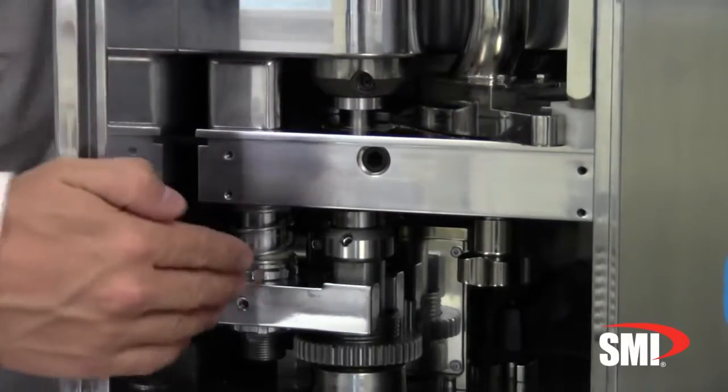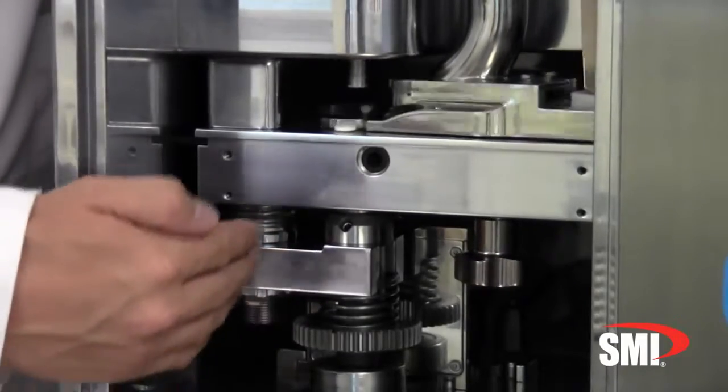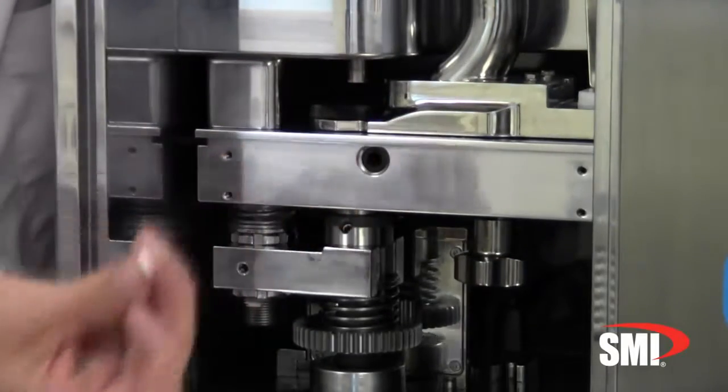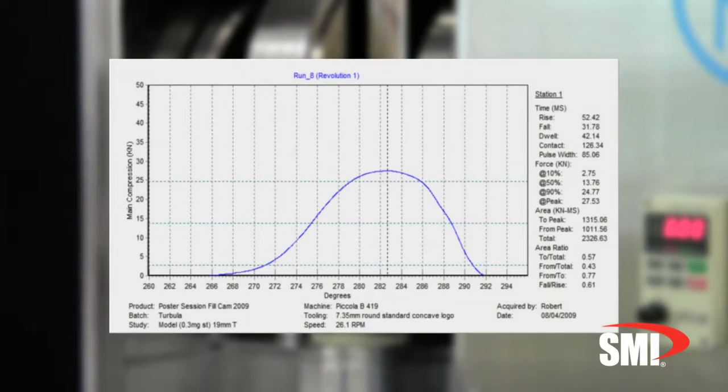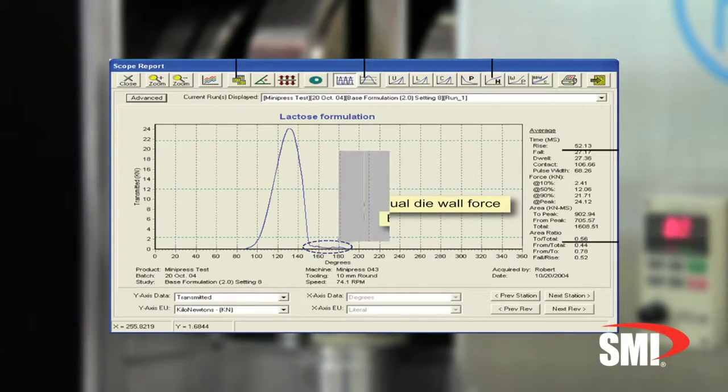When product is limited, the Director software will allow the analysis of a single tablet. The report includes detailed scope analysis for each transducer, including the residual die wall force after the decompression event.